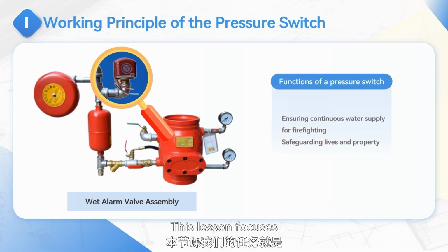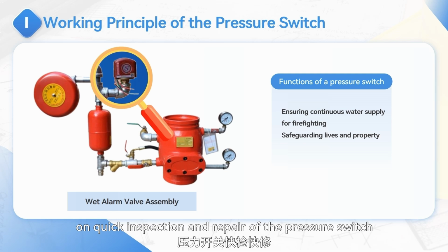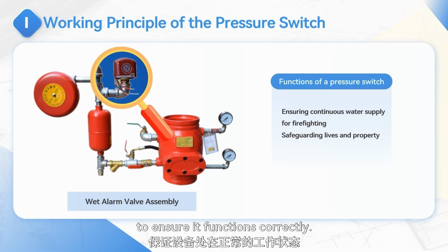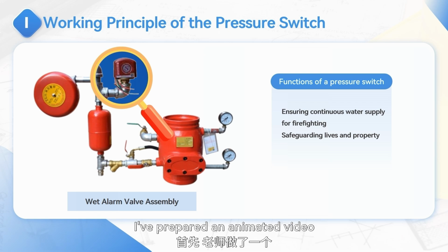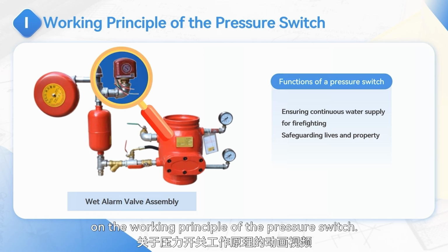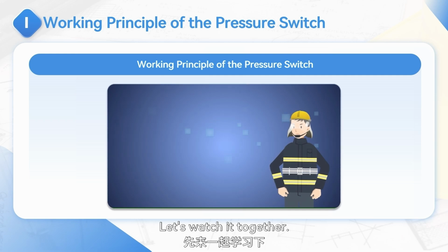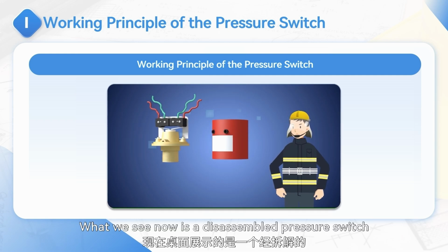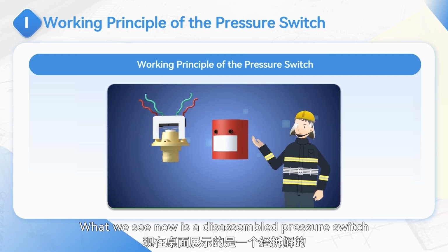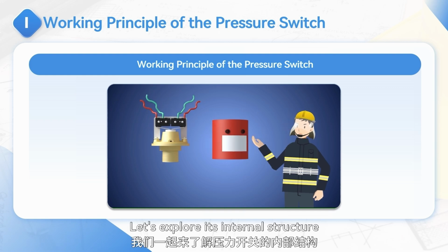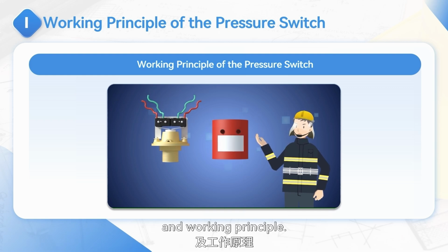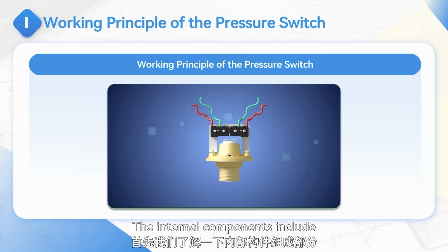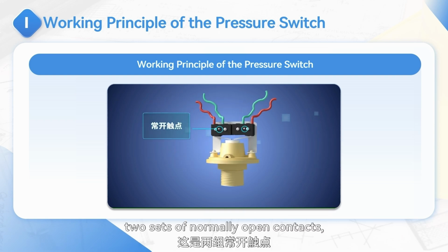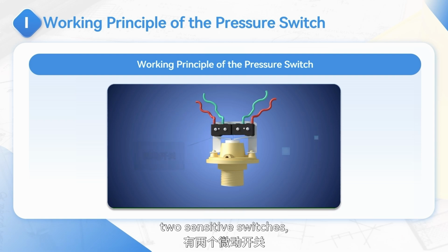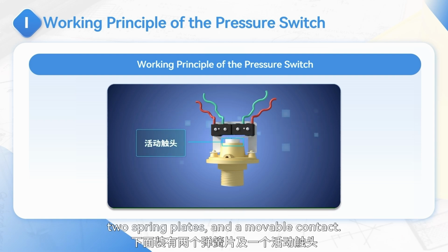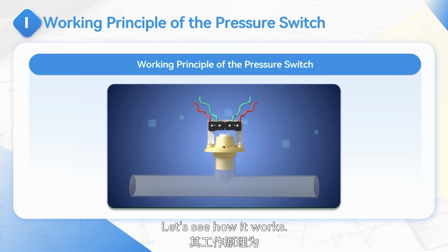This lesson focuses on quick inspection and repair of the pressure switch to ensure it functions correctly. I've prepared an animated video on the working principle of the pressure switch. Let's watch it together. What we see now is a disassembled pressure switch from an alarm valve. Let's explore its internal structure and working principle. The internal components include two sets of normally open contacts, two sensitive switches, two spring plates, and a movable contact. Let's see how it works.